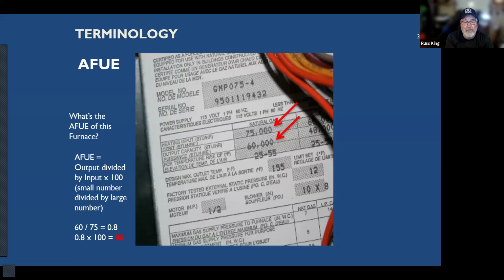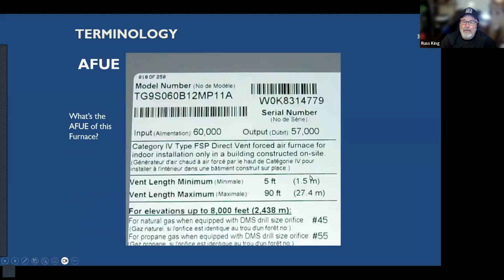If you've heard the term condensing furnace, but now you've got to do something with that water. Because it was a combustion product, it's not pure water. It's got some nasty stuff in it. It's not acidic. It's basic, I think, and so you can't just put it anywhere. You have to be a little bit careful where it goes. But anyways, that's what we call a condensing furnace. But the cool thing is they're able to capture a lot of that heat that would otherwise go up through the attic, and the efficiencies go up dramatically.